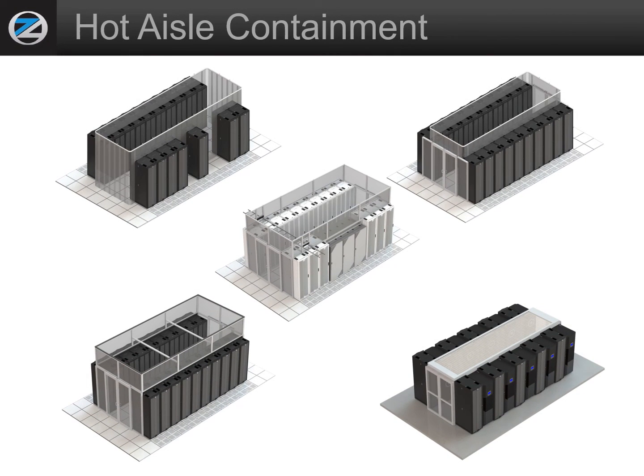Hot aisle containment is really based on a few key factors: the ability for air to be isolated to the return of the HVAC units for maximum efficiency, and if the HVAC units are cooling a human-defined space or a frequently used space for NOC or repair and monitoring. These examples show much of the same equipment from the cold aisle, but also include options for return air to travel into the common air return space directly to the wall-mounted HVAC units. Hot aisle, just like cold, can be performed on raised or concrete floors.